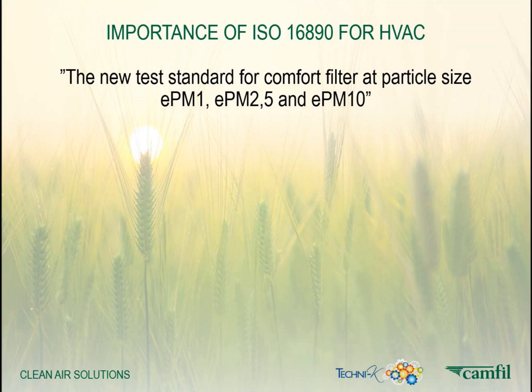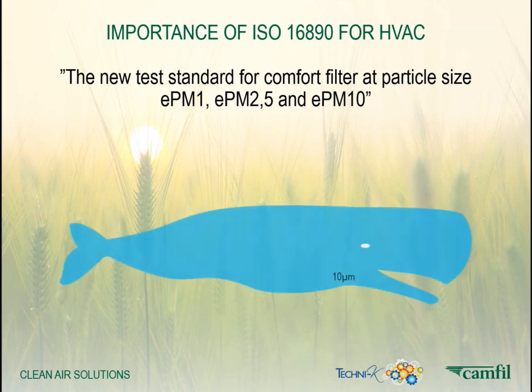ISO 16890 is a new standard for testing comfort filters. It's a huge filtration difference between ePM2.5 and ePM1, even if the efficiency percentages look the same. In the picture, you can see a correlation between PM-sized particles, but to put this into context, if a 10-micron particle would have the same size as a sperm whale, then an elephant would be equal to 2.5 and a human would be equal to 1 micron.